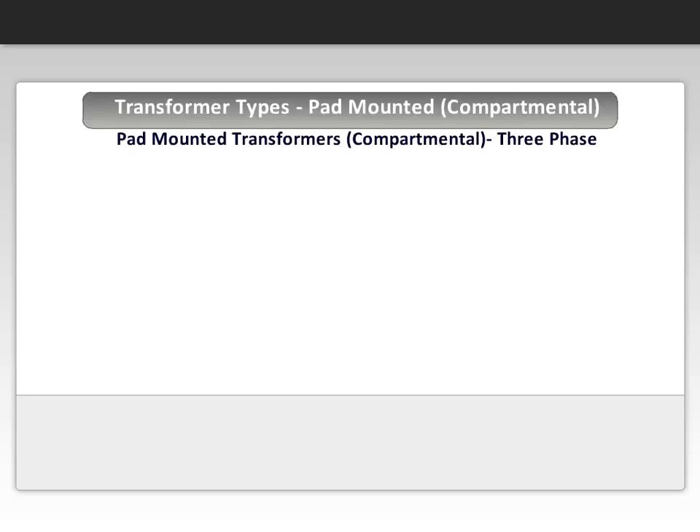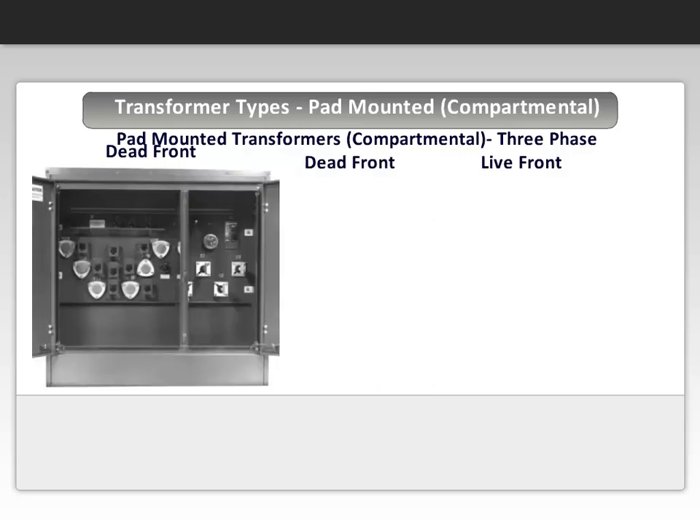It is critical to understand the difference between the two types of compartmental transformers: live front and dead front. The next two slides will help you understand the concept. A dead front transformer is one that has high voltage bushing wells and inserts. Another way to describe it is that it has two-piece bushings that are used with elbows and allow connections without the operator being exposed to any live parts.